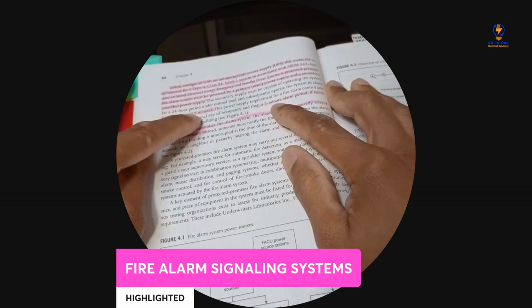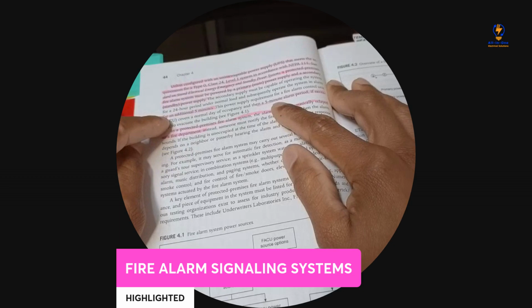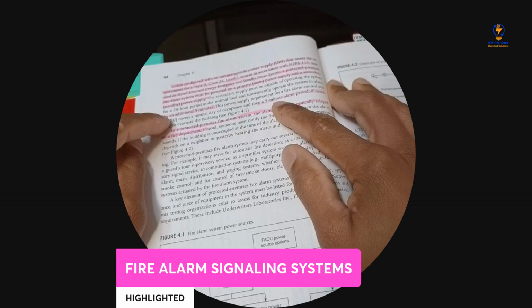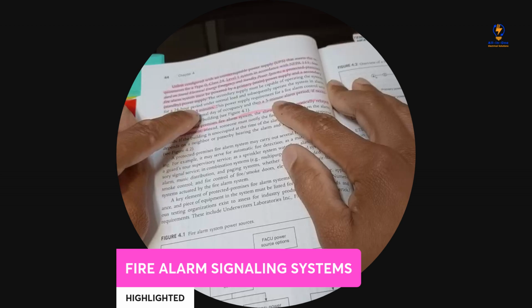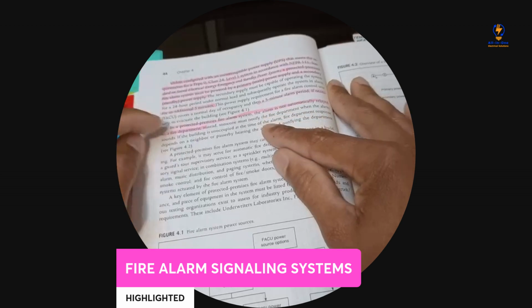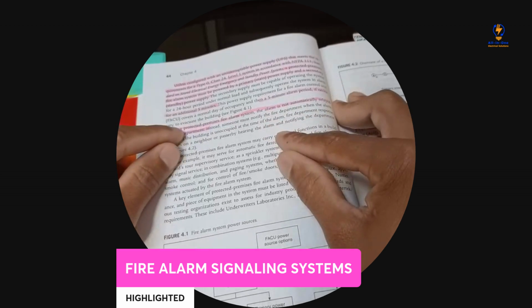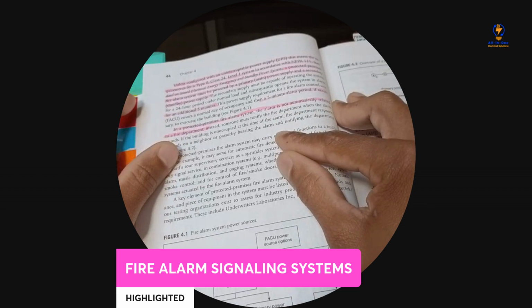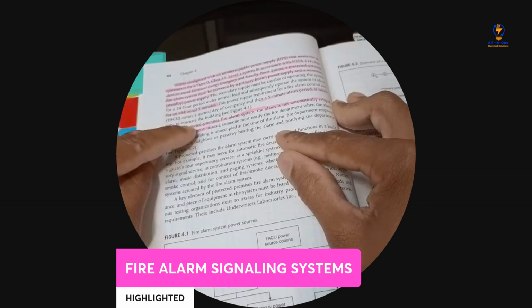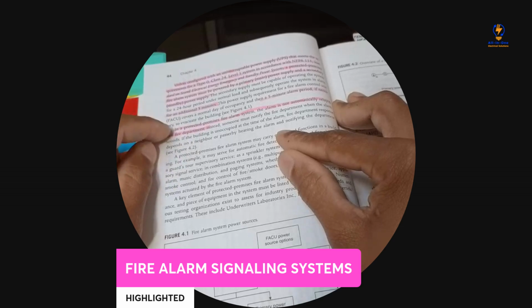The secondary supply must be capable of operating a system for a 24 hour period under normal load, and subsequently operating the system in alarm for an additional 5 minutes. Highlight that, and then the next paragraph: in protected premises fire alarm, the alarm is not automatically relayed to the fire department. That's page 44.